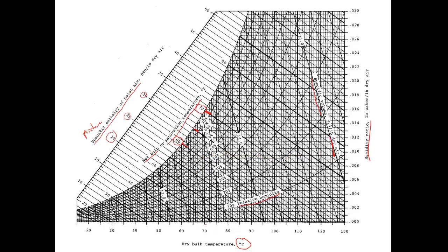So as I showed you on the other chart, we have the 70 degrees Fahrenheit for the dry bulb. If we look up where that hits, and I kinda gotta get through these relative humidity percentages, but right here it hits that 70 degrees Fahrenheit for the wet bulb temperature. So right there it shows us is the dew point temperature. All right, so where we'd have, where we'd hit a certain dew point if we travel across from left to right. So if we're going this way on the chart, so say we start out here at 100 degrees for our dry bulb temperature, and there's 100 degrees, go straight up. And we're gonna maintain the humidity ratio. So the humidity ratio is pounds of water, or mass of water to the mass of dry air. And that's not gonna change until something starts condensing. So if we cool it, starting at 100, and if we cool it, it's gonna move to the left until it hits our dew point, our 70 degrees. So that's why it's called a dew point.